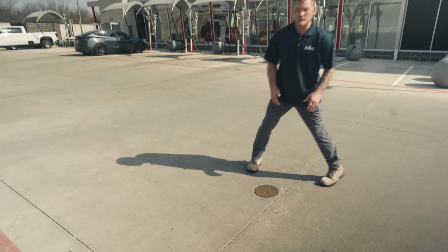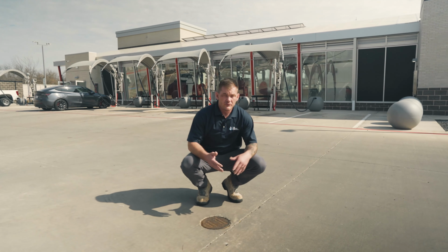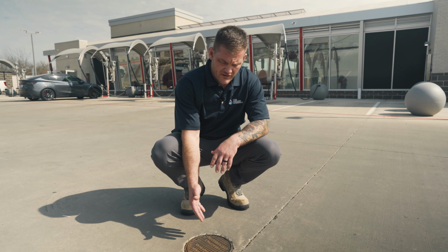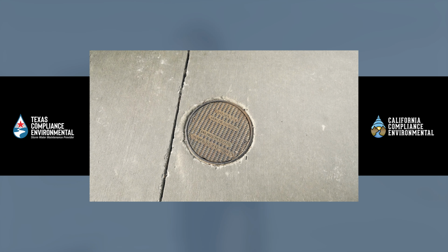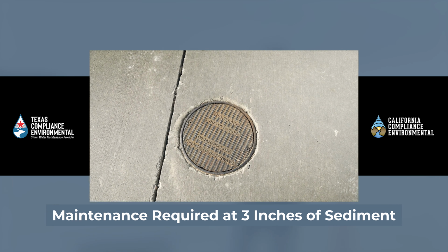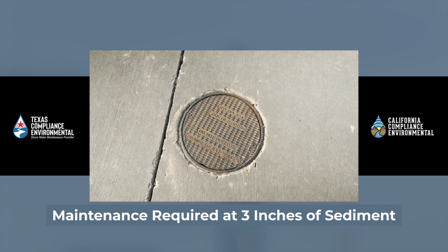Part of this stormwater system, you have a test port. You have the maintenance access, and then you also have the test port. We would send our sediment rod down here, test the sediment. Once you get 3 inches of sediment in this system, maintenance is required.